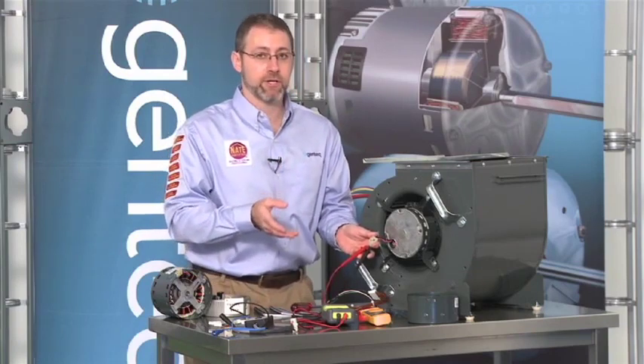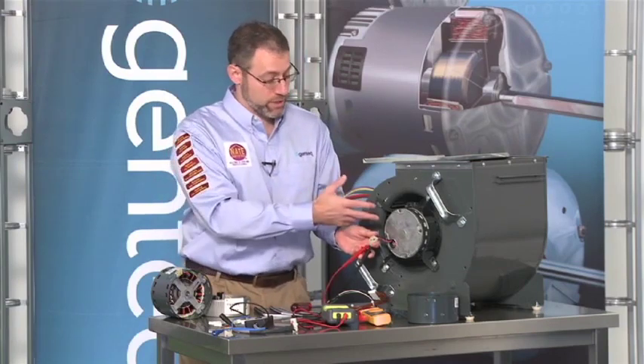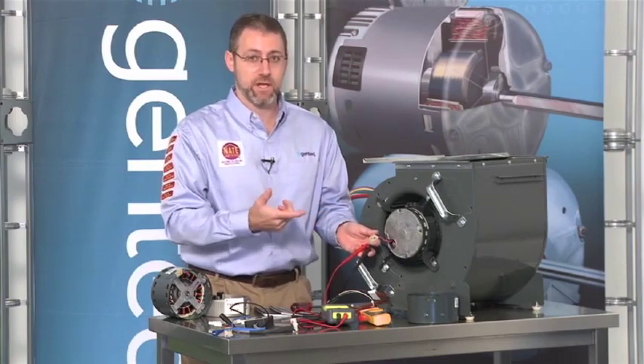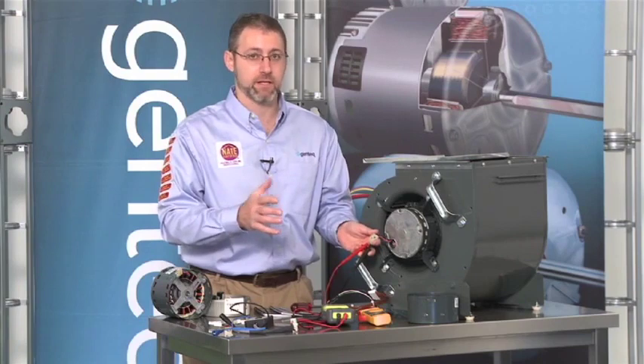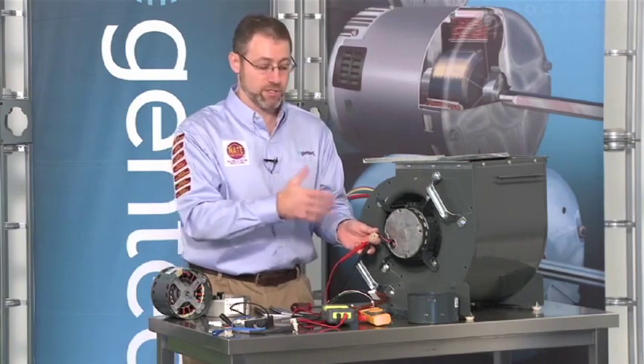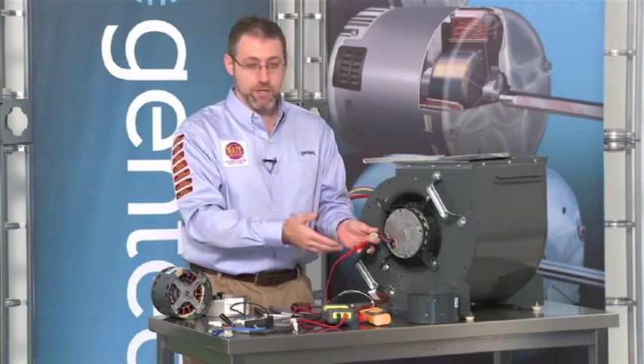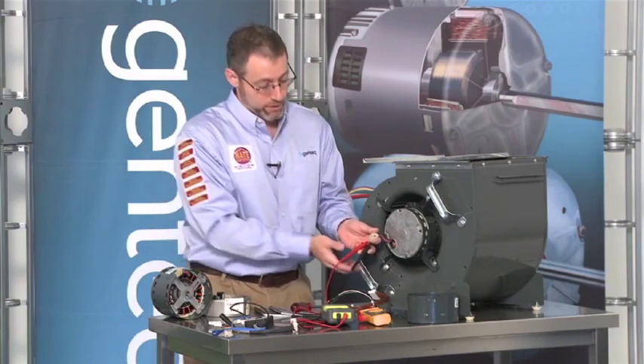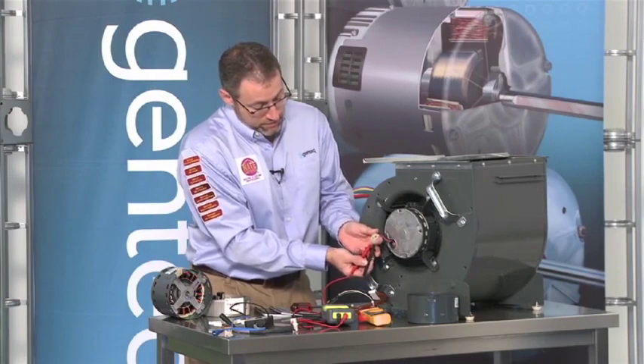The only other criteria for any three-phase motor, including ours, is that all three of these readings be the same plus or minus 10%. In other words, your meter is never going to read the same 5 ohms each time you check it. So as long as all three readings are the same and it's below 20 ohms, we have a good motor.